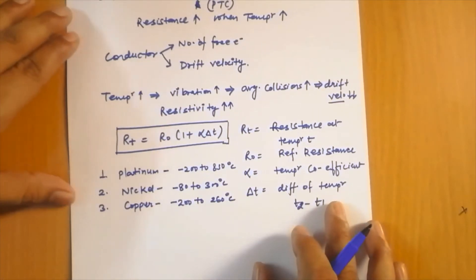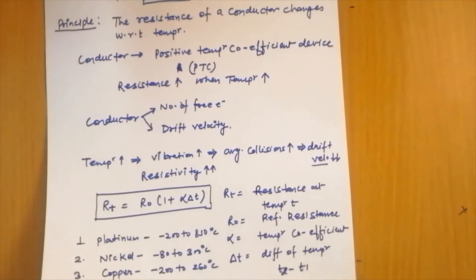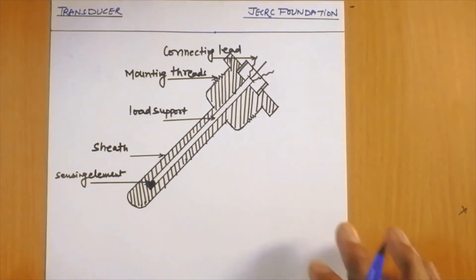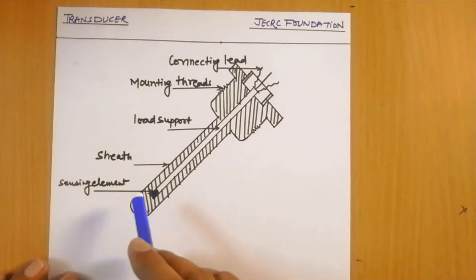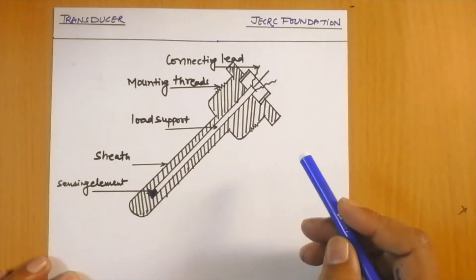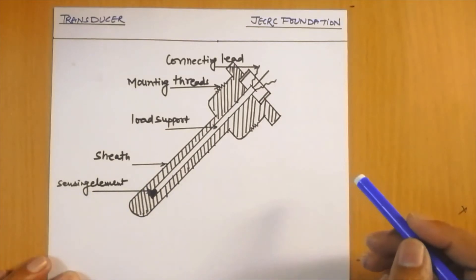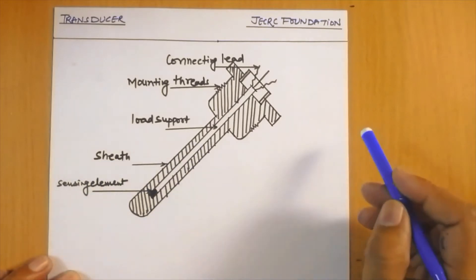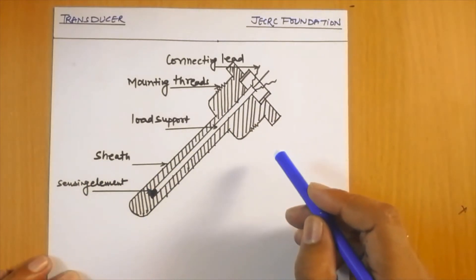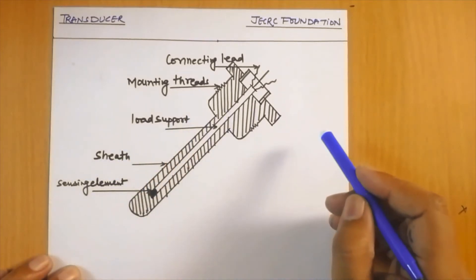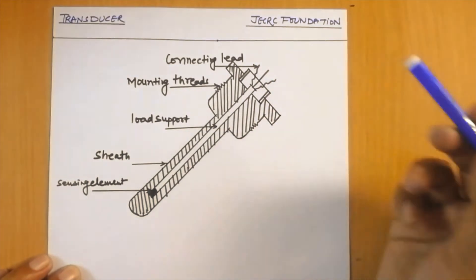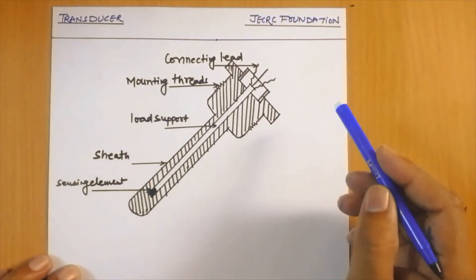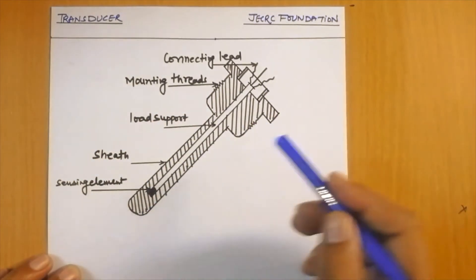The basic construction of an RTD consists of a sensing element used to sense the temperature — generally copper, nickel, or platinum. A protective sheath protects the device from mechanical damage or contamination. A lead support holds the connection leads that connect to the external circuit, and mounting threads connect the RTD to any external device.